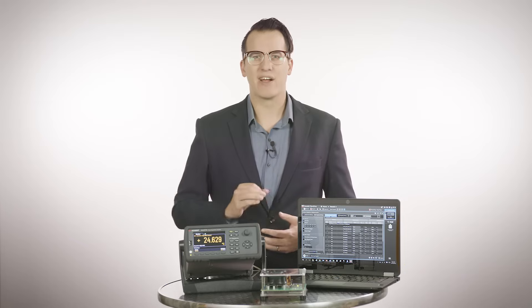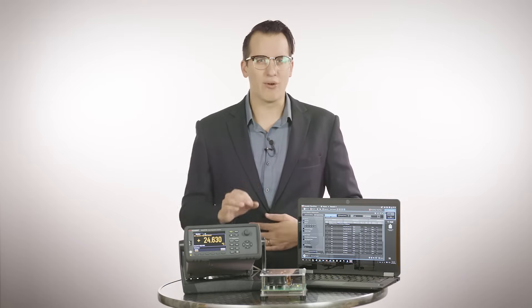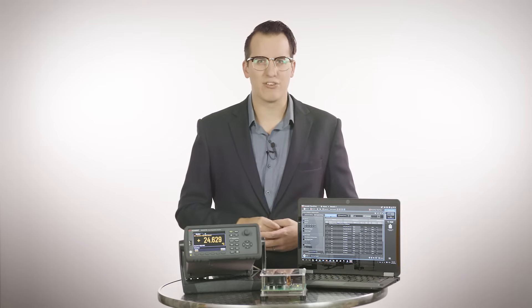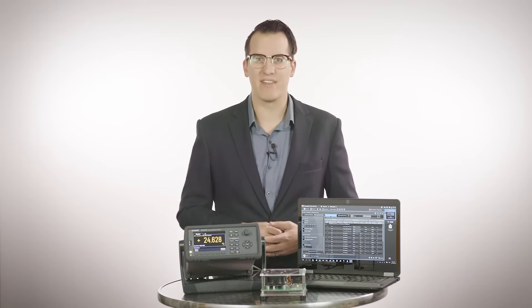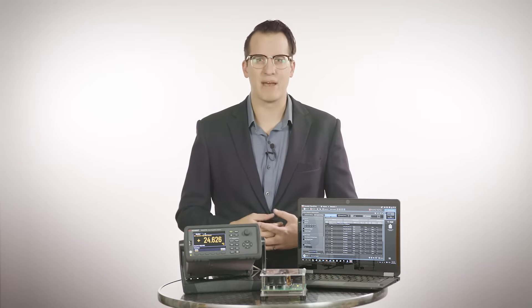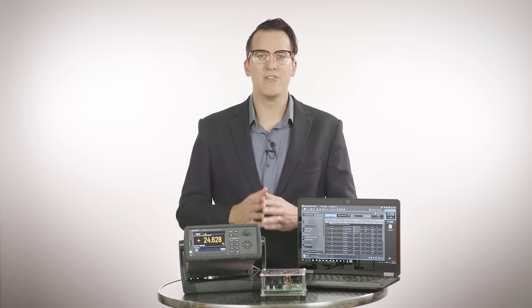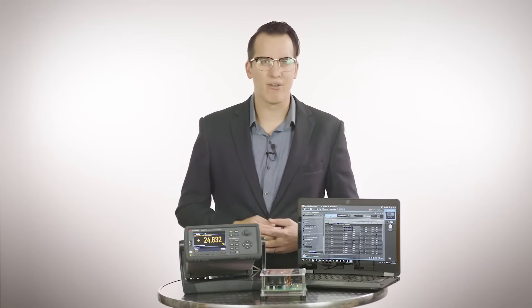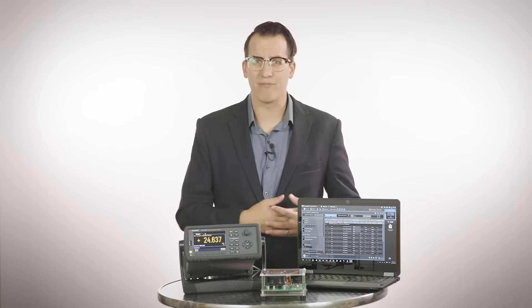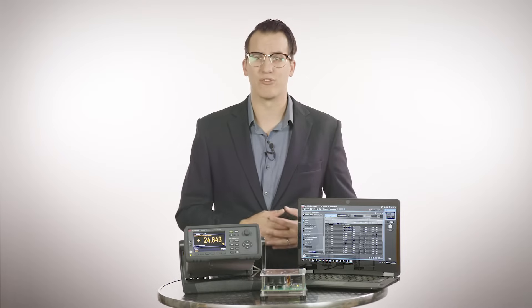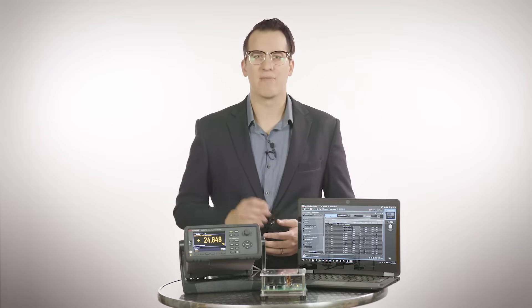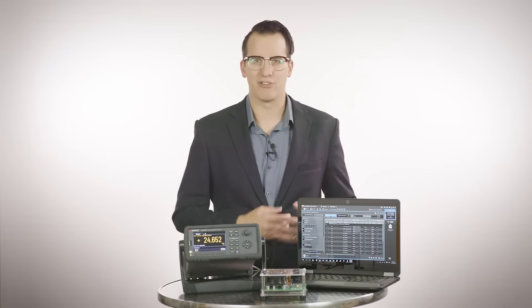The DAQ970A also has up to 90% better accuracy for voltage, current, and resistance measurements. It comes with a new auto calibration feature, which compensates the internal DMM and the new DAQM907A multi-function module for drifts caused by time and temperature changes.